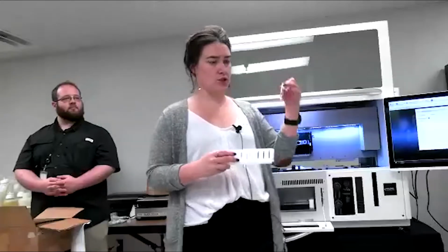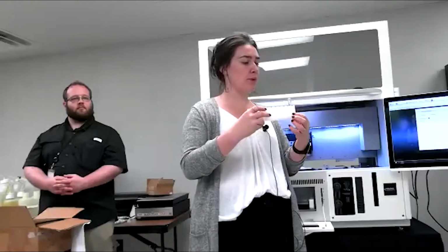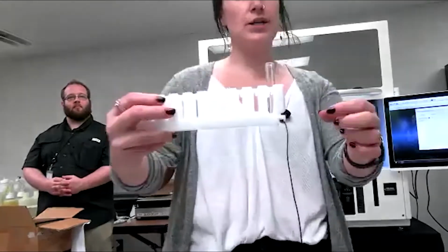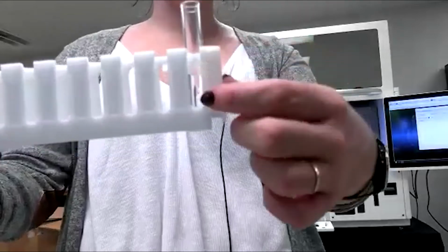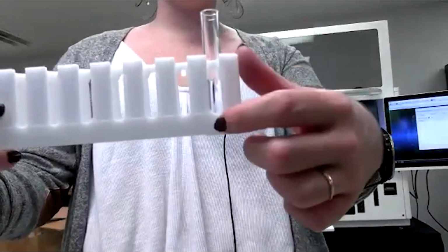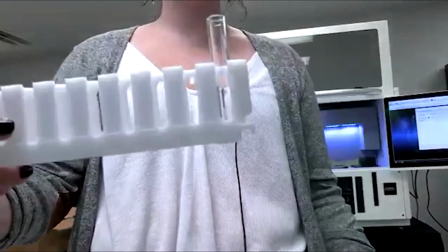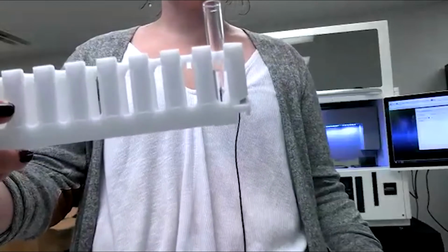I can't promise it because I don't know what kind of caps you're using, but especially the rubber caps, I've left those on a time or two, and it's never caused any more problem. More robust than our old needles. Yes. And then with your barcodes, this is just water for now, but as long as your barcode can clearly be seen, which camera are we using right now? As long as your barcode can clearly be seen through this slot, then the machine should be able to read it without any issue.